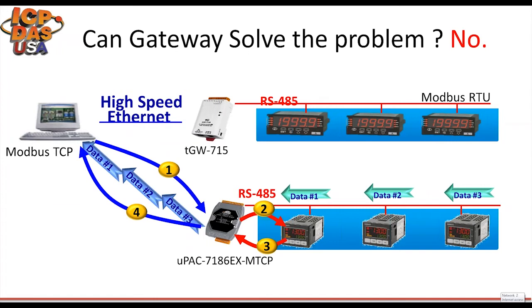So let's talk about the solution. This is our TGW Modbus TCP to Modbus RTU Gateway. We have similar products such as I7188, EX-MTCP, or TGW 715 — they are all Modbus gateways. For this type of product, it is required to set the baud rate of the COM port on the gateway and the ID range of the Modbus RTU devices managed by each COM port. When performing communication on the PC, the IP address and Modbus ID of the gateway are specified. When commands are sent from Modbus TCP to the gateway, they will be bypassed to the Modbus RTU device on the corresponding COM port.